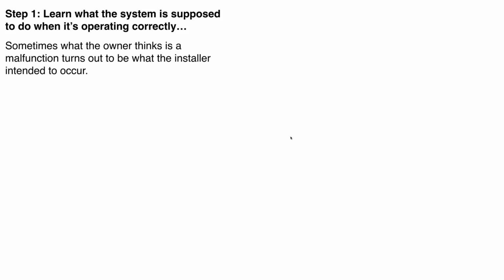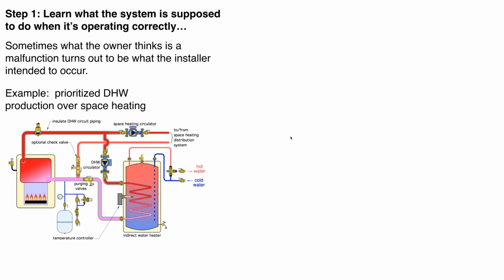So step one, let's start with what is the system supposed to do when it's operating correctly? We've seen techs go in with a misunderstanding of what the system is supposed to do. You've got to learn what it is supposed to do before you can try to correct why it isn't doing that. And sometimes an owner doesn't really understand that. Sometimes the owner thinks there's a malfunction and it turns out to be not a malfunction. And here's a good example of that.